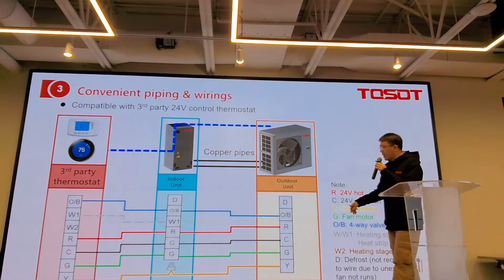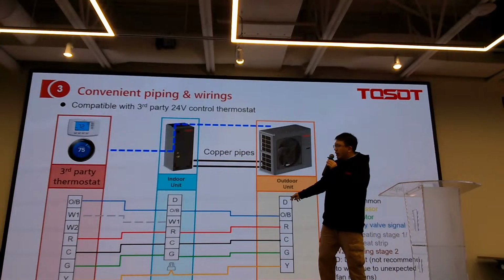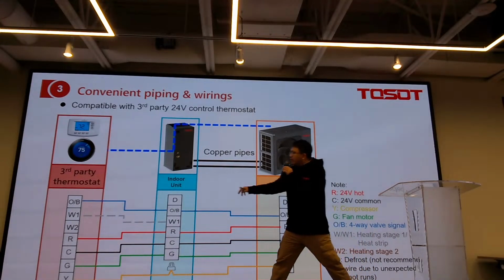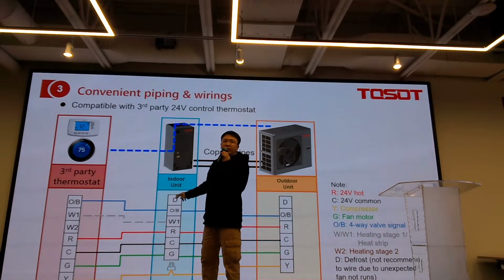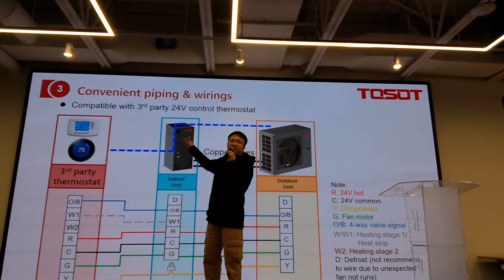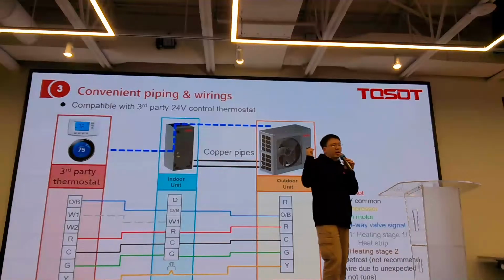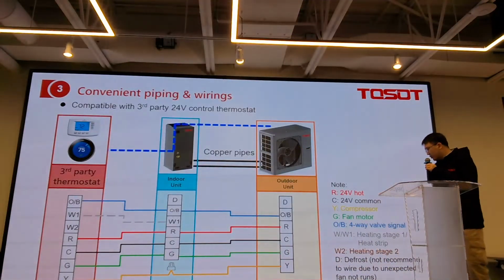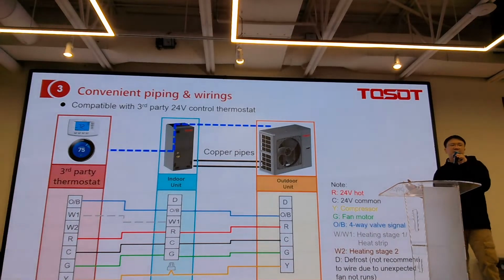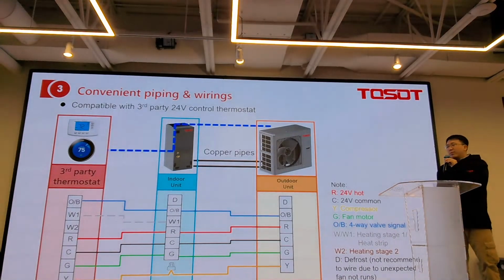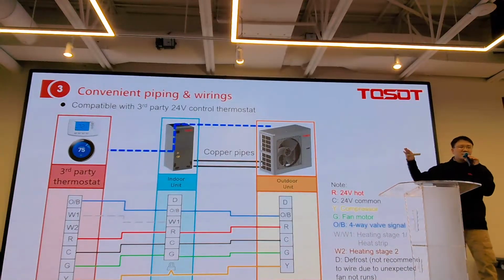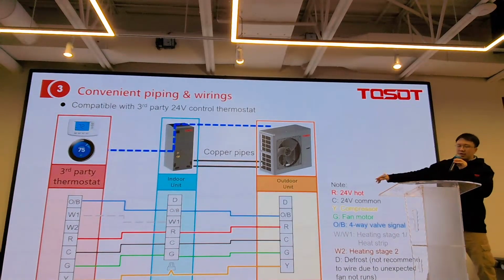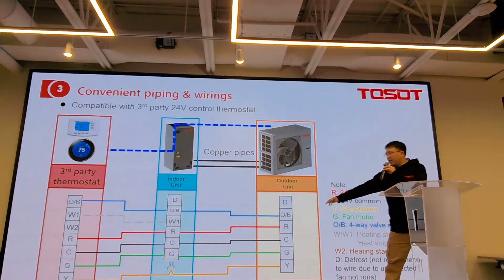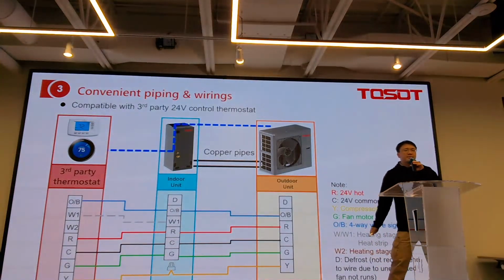And this D is, if we get 24 volts from here, you just stop the fan. If the customer complains, it's not that easy to make them understand why my fan is stopped. So our recommendation is, if you are not familiar with our system, you don't need to wire the D. Just leave it open. It's okay.